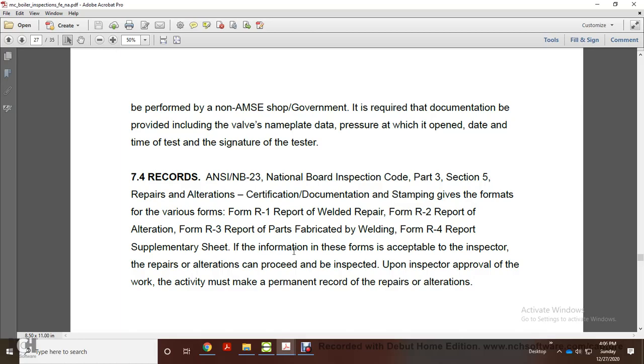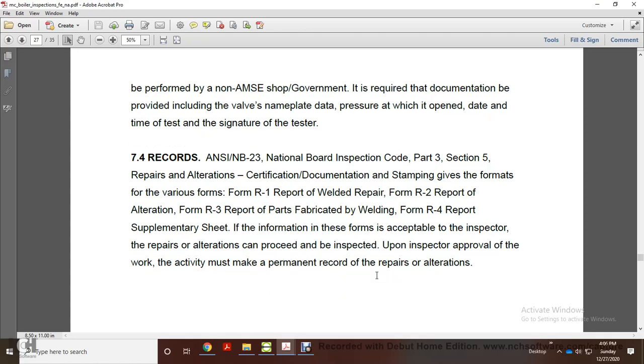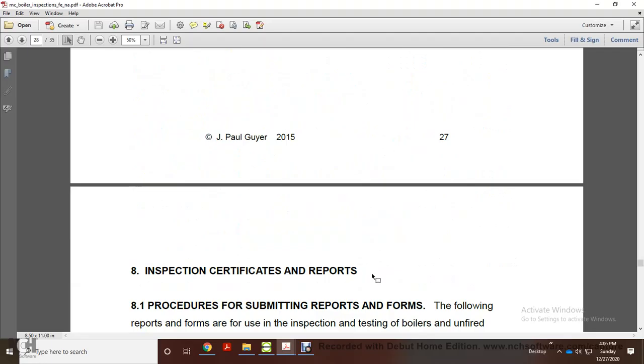Alright, 7.4 Recorder Records, ANSI/NB-23 National Board Inspection Code Part 3, Section 5 Repair Alteration Certification Document Stamping of the forms. Form R1 Report of the welded repair. Form R2 Report of Alteration. Form R3 Reports of repair. Reports of parts fabricated by welding. Form R4 Report of supplementary sheet. Information in these forms acceptable to the inspector of repair alteration can proceed with the inspection. Upon inspector's approval of the work or the activity must make the permanent record of the repair alterations.